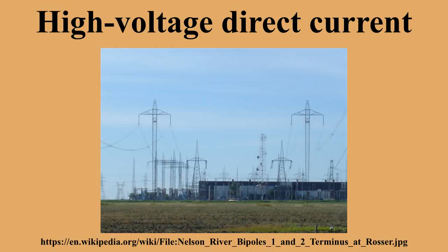At smaller transmission distances, the losses in the converter stations may be bigger than in an AC transmission line for the same distance. The cost of the converters may not be offset by reductions in line construction cost and lower line loss. Operating a HVDC scheme requires many spare parts to be kept, often exclusively for one system. As HVDC systems are less standardized than AC systems and technology changes faster, in contrast to AC systems, realizing multi-terminal systems is complex, as is expanding existing schemes to multi-terminal systems.